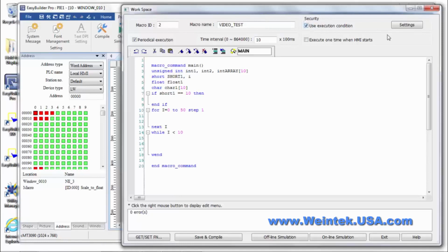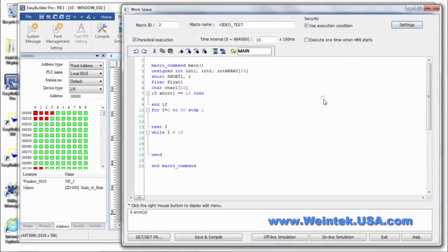You can use what they call a security condition, which is just a disable condition that you can set using an internal bit from the HMI. You can make the macro execute one time as the HMI boots by checking here. And of course, times 100 milliseconds, this is the cycle frequency.